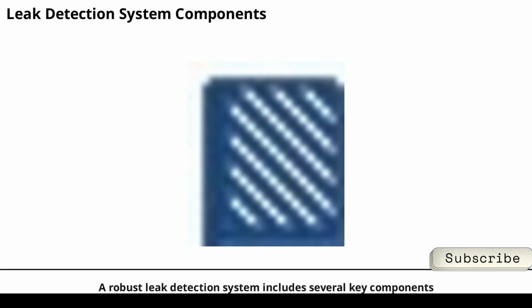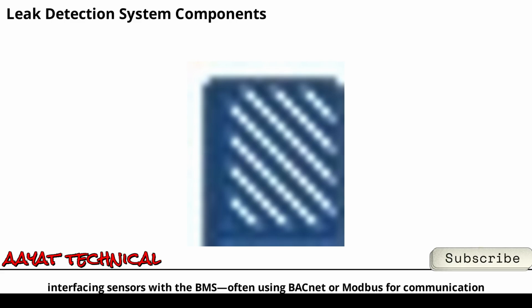A robust leak detection system includes several key components. Leak detection cables sense moisture along their entire length, making them ideal for covering large or irregular areas. Point sensors are used for specific locations, like under a piece of equipment. The leak detection panel acts as the brain, interfacing sensors with a BMS, often using BACnet or Modbus for communication. Alarm outputs, such as dry contacts or digital signals, alert the BMS when a leak is detected. Together, these components create a comprehensive safety net for your building's most vulnerable spaces.